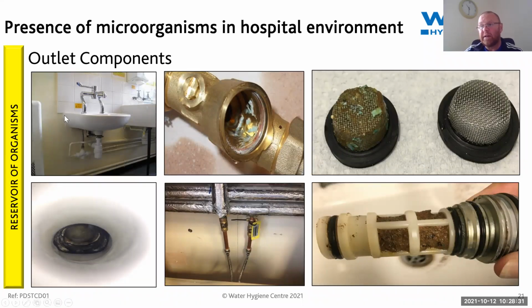In this photograph on the left, we've got a Belfast sink on the right, and a wash hand basin on the left, which looks to me as though it's a thermostatic mixing tap. But if you look down here, that's already got a thermostatic mixing valve on it. So that doesn't really add up, does it? We've got a thermostatic mixing valve feeding a thermostatic mixing tap.